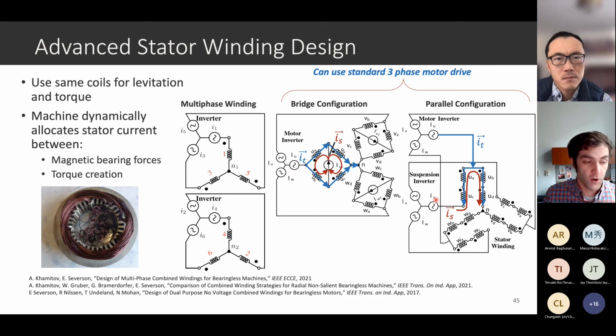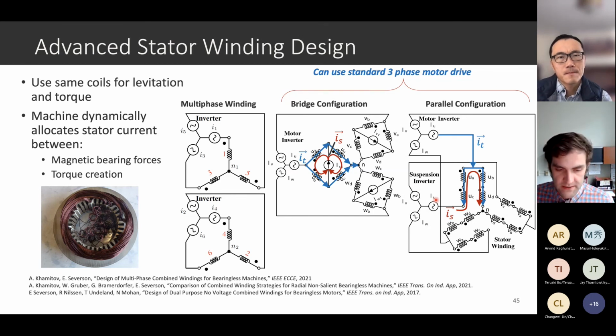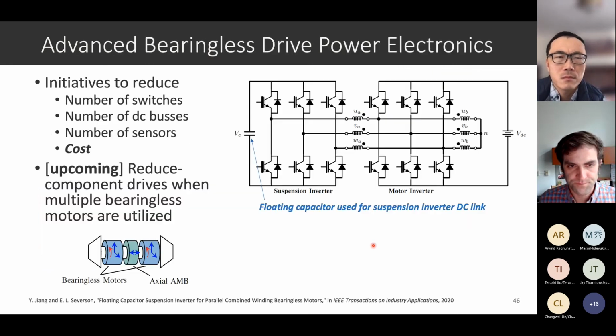It's been shown in numerous studies that doing this has tremendous improvements in motor performance. You're suddenly able to get designs with high power density compared to designs with separated windings. These designs can reduce copper losses by upwards of 39%, so it's a big deal for the performance capabilities of the machine.